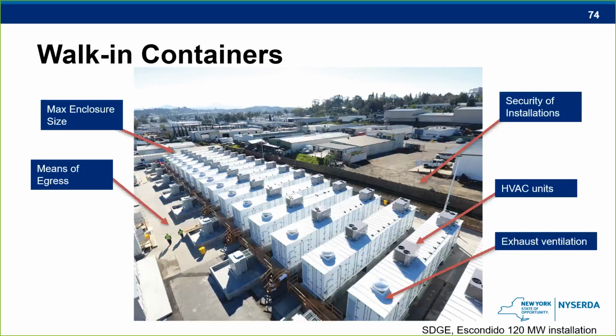So outdoor systems are typically housed in one of two ways: walk-in containers or cabinets. So this slide is showing an example of walk-in containers. And here you can see the maximum enclosure size we discussed earlier. They're about the size of a standard shipping container. For a little bit of scale, if you can see on the left-hand middle-ish side of the screen where that first arrow is pointing, the two little green dots are actually people walking down the aisle. You can see the fence around it, how it's secured from outside access, and the aisles are nice and wide and provide an adequate means of egress.